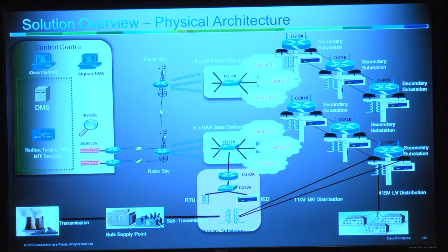And the WiMAX network was radiated out to 9 primary substations, which effectively acted as the WiMAX base stations. And then from those 9 primary substations, we interconnected 200 equivalent secondary substations, as you can see at the bottom, per the transformers on top of the overhead power lines. All of those were interconnected via the WiMAX sector design.